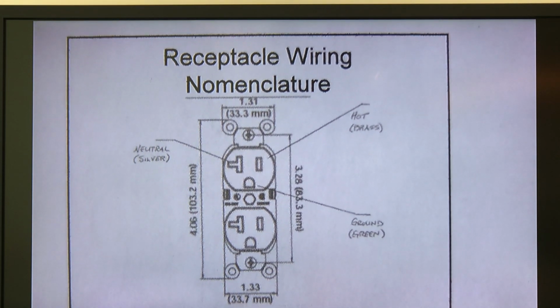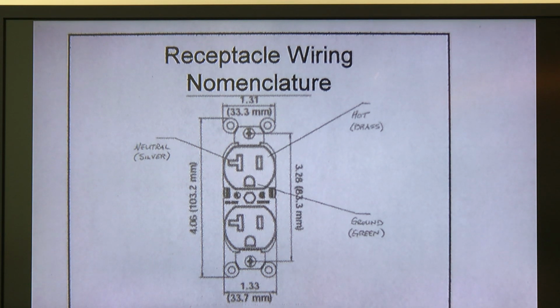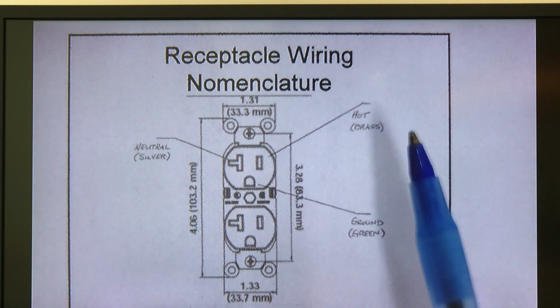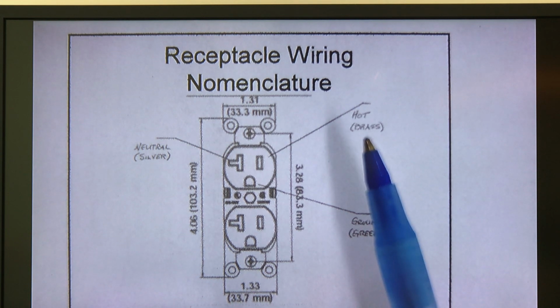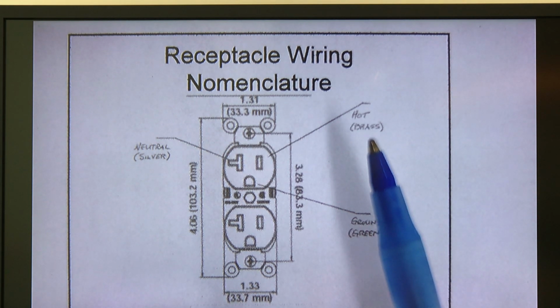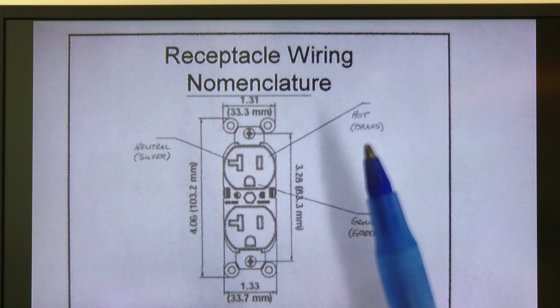Now, as you might expect, it makes a difference what you plug into it or how you hook it up. And so the conventional nomenclature for a device like this, and we'll use a 20 amp receptacle because that way you're clear about what the neutral is, there are three types of connections. You have your hot wire, and that goes to a part of the connector that's made out of brass, kind of a coppery color. So that's your hot connection. That's the one that goes to the circuit breaker in your circuit panel.